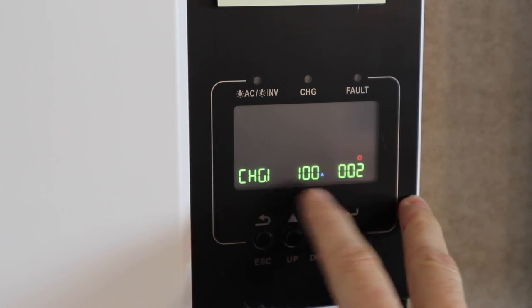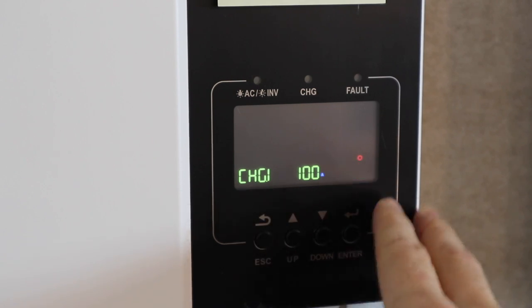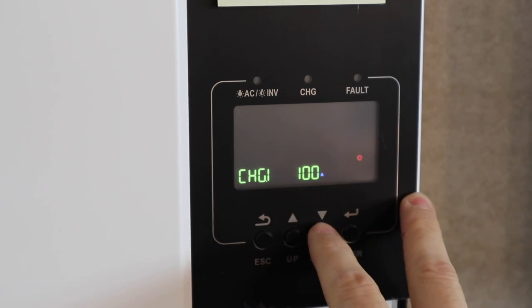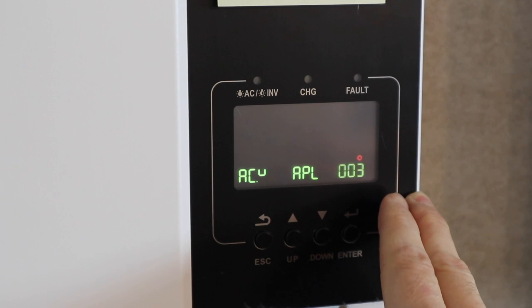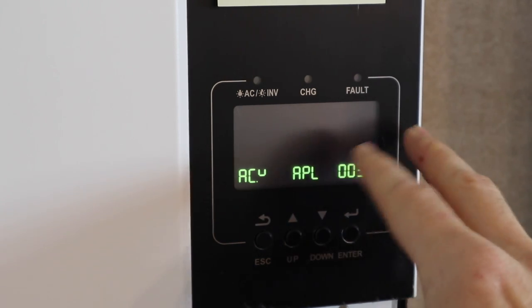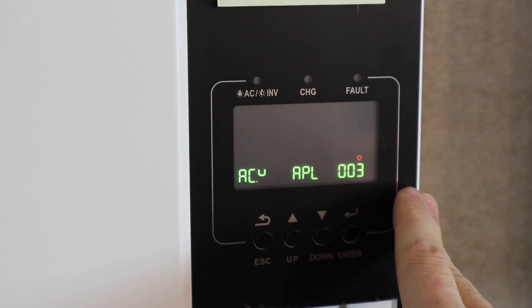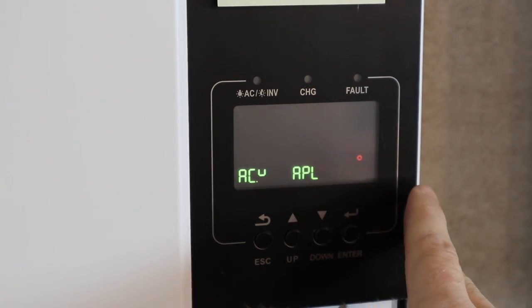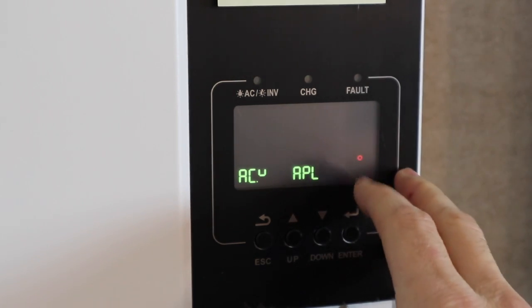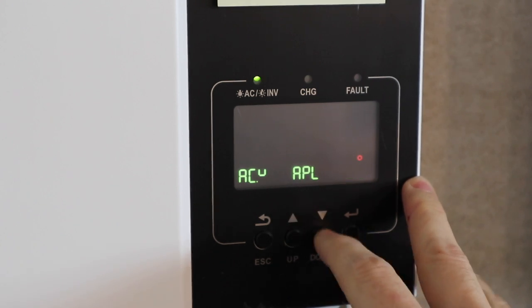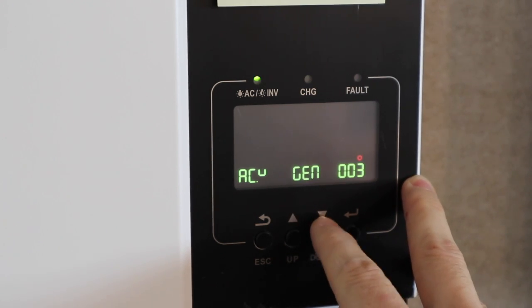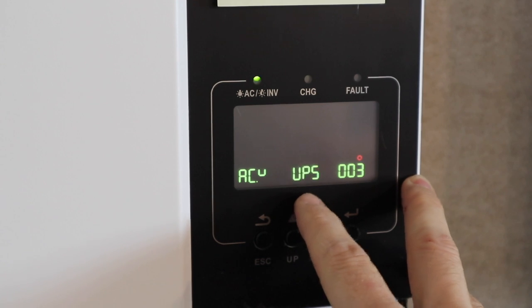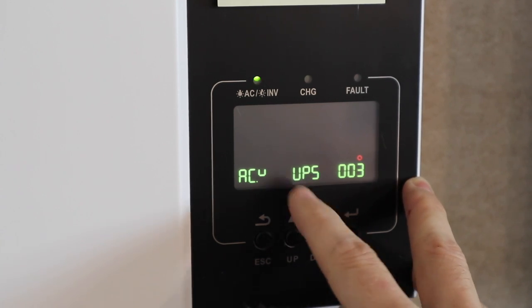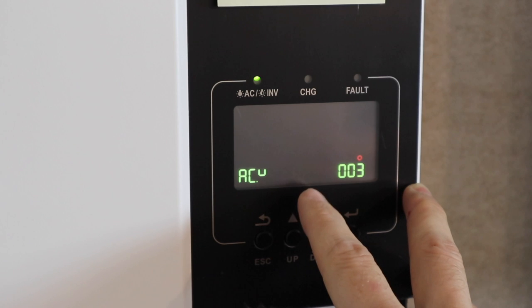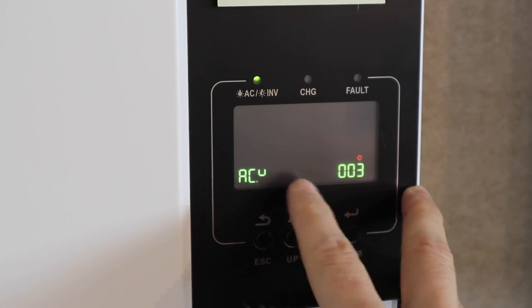Let's move on. So we have lithium batteries. This option two is for lead acid batteries only, so we're going to skip over that. Option number three is the quality of the voltage that's coming in. Obviously generators have some dirty power. It's very clean power that you're getting from the grid. But for us, we're going to go in here and scroll down to UPS. That is a recommended setting for anybody off-grid from Signature Solar. Obviously, we don't have a generator and the other one is the default. So we're going to leave it here.